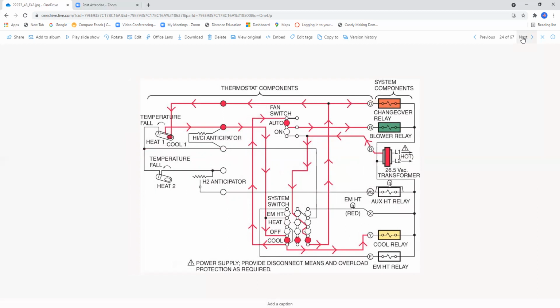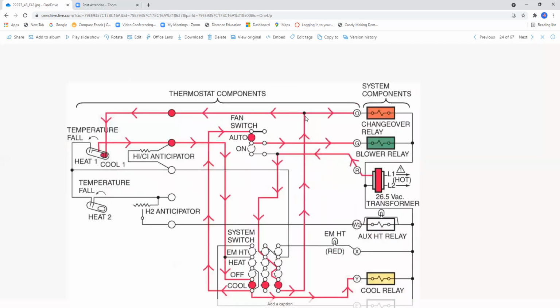Okay, here's another diagram. In this case, we're showing the cooling position. So this would be the diagram showing what is taking place. Notice that the fan switch is in the auto position here. Okay, so auto position, and of course you got your cooling taking place here. Emergency heat is off, got our power. Now, interestingly enough, I don't see the common terminal shown here. Most thermostats today, in order to get rid of the battery, require a common terminal. Okay, I do not see it here in this diagram. And in this case, the O terminal indicates a changeover relay.